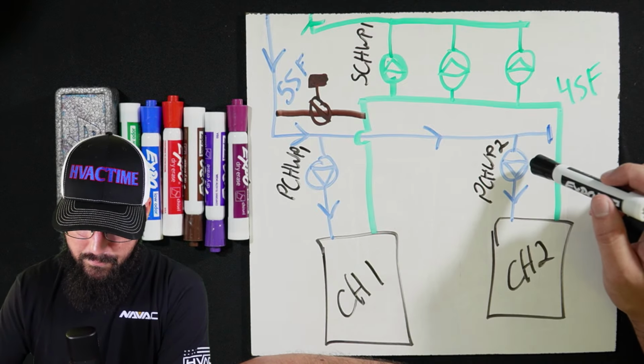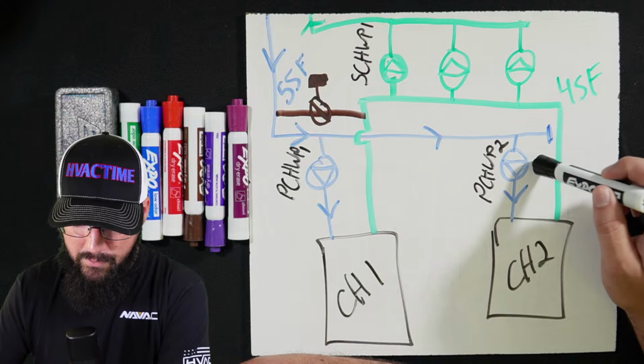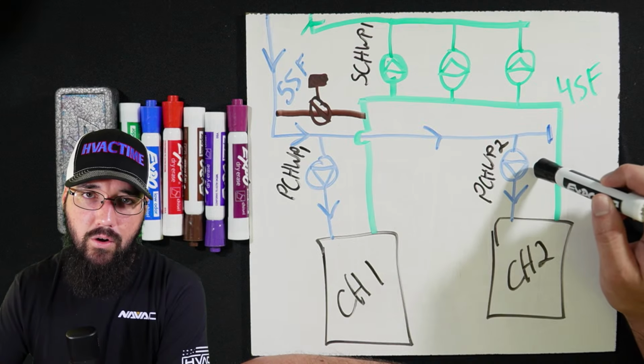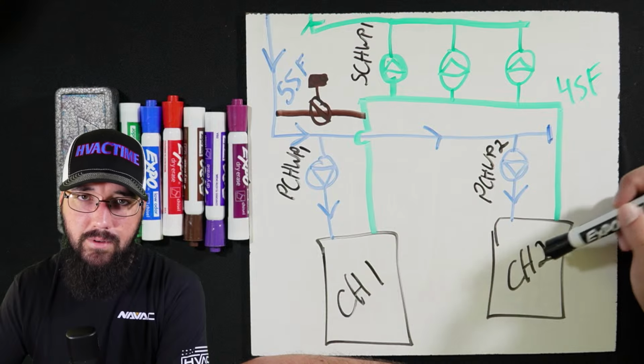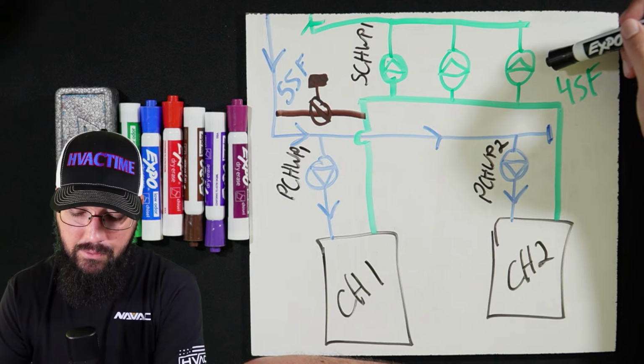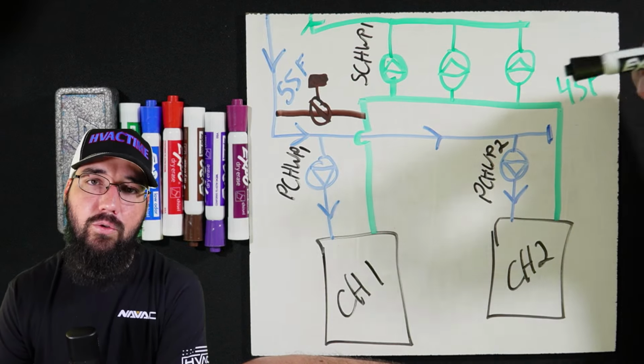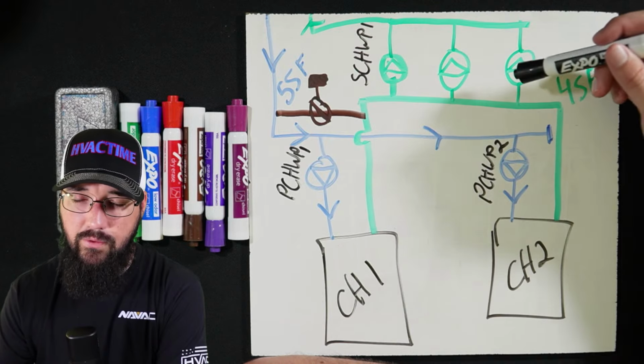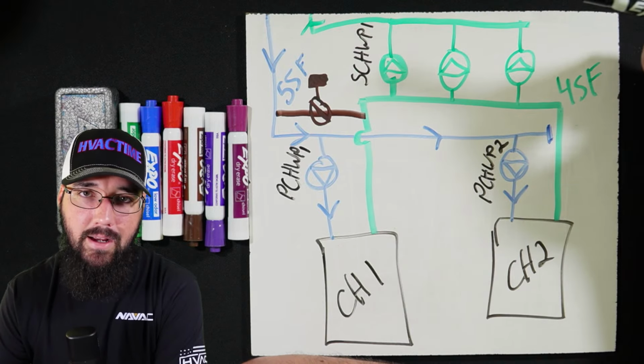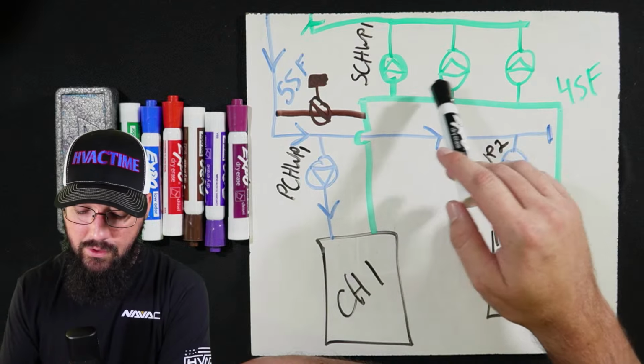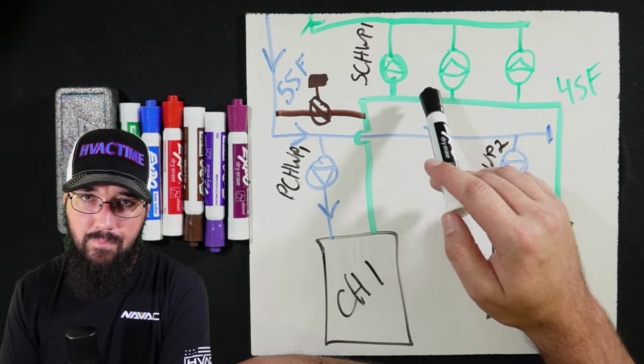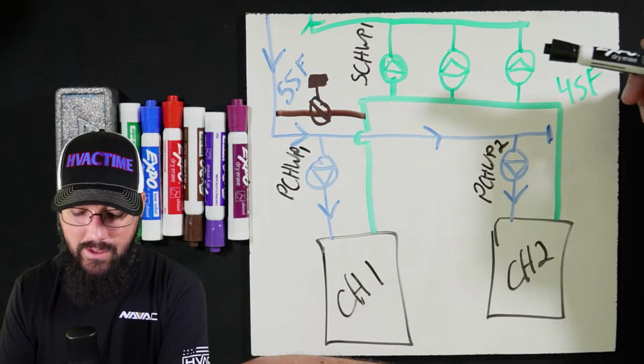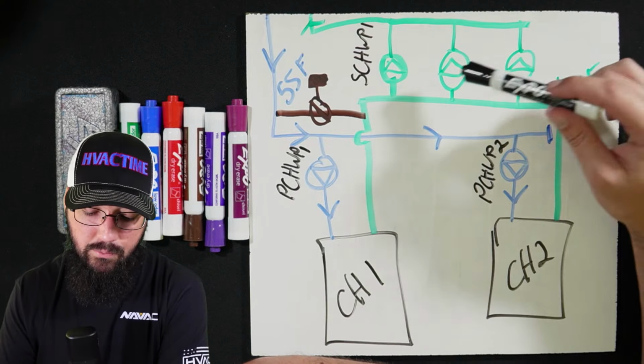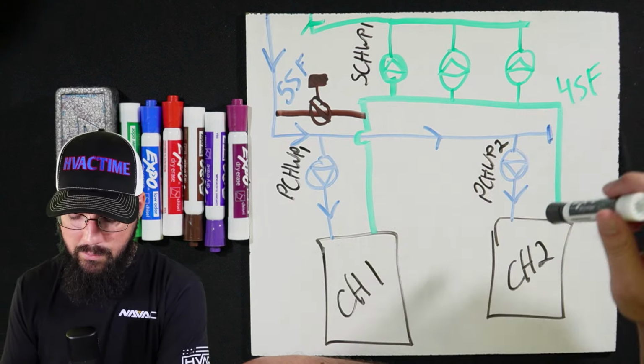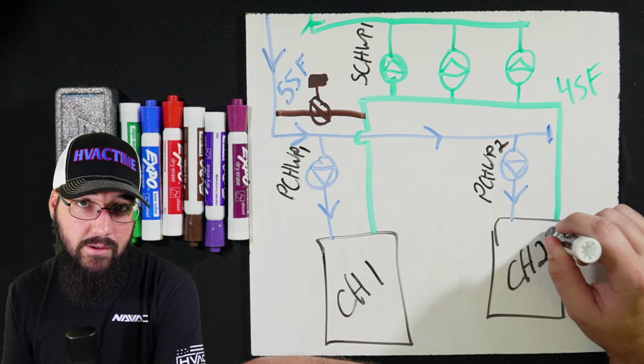So the primary's job is to serve water to the chiller itself. That is it. The secondary pump's job is to serve water to the loop, and it's going to take the water from the chiller and push it back out to the load. Now, these could stage however needed. At a really high load state where we've got major demand on the loop, we may need all three pumps. We may only be running one chiller at the time.